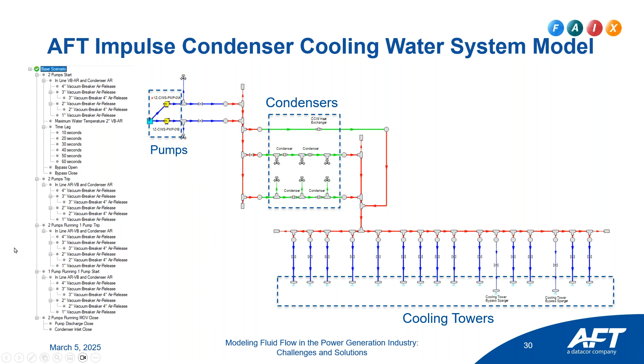Okay. This is a screenshot of the scenarios. I think there were 47 scenarios that were done by this engineer, looking at a two pump start, a two pump trip, and then a single pump trip, one pump running and one trip, etc. Different types of possibilities for managing the air for low pressure protection right here around the pump discharge and also around the condensers. Okay, so this is very common. I've seen this many times, hundreds of times. People using Impulse on systems like this, a very common thing. Nothing terribly unique about it, other than it's something that AFT can do and not everybody can do with our Impulse software. A lot of other companies just don't get into that, and we do. And we can take your Fathom model just like this and bring it in and kind of start up for the cooling and the water hammer prediction.